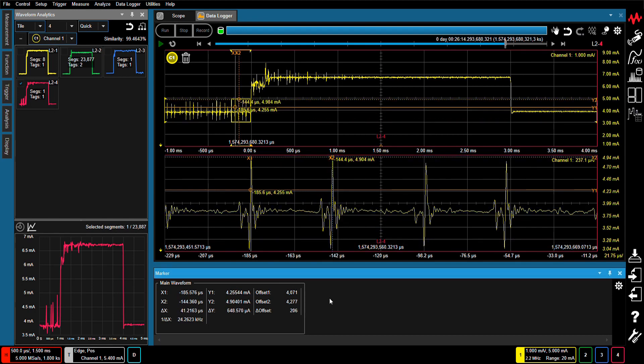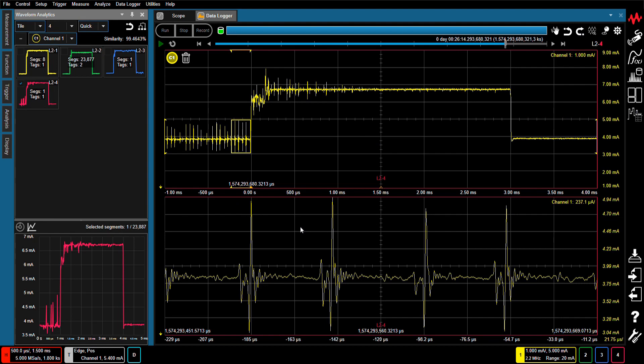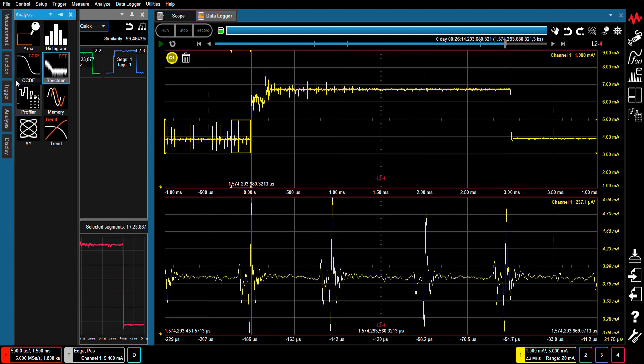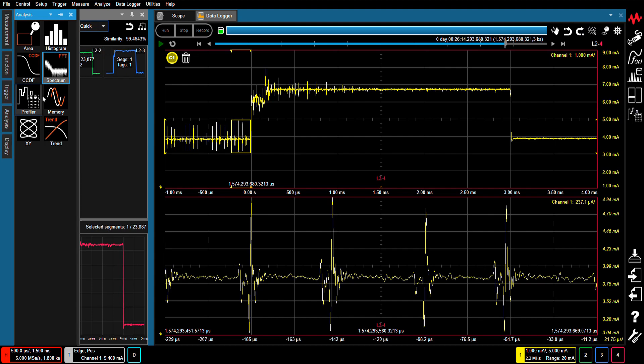As you can see, there is a periodic noise. You can check the periodic time and frequency using the marker functions. The CX3300 also has a variety of powerful analysis functions that can be used to perform analysis on a waveform of interest selected from those displayed by the Anomalous Waveform Analytics function.